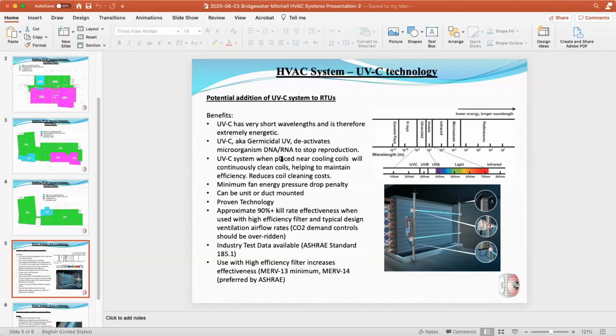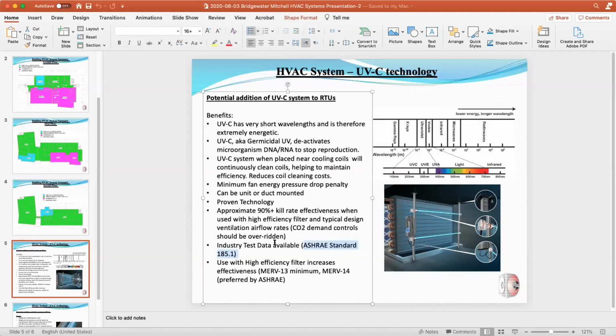That is what's used. It's generated by a bulb that has mercury vapor, and it's generating UV light. They're typically installed in the air handling units on the supply side, at the cooling coil, or within the supply ductwork if it cannot fit in the air handling unit. Approximately, and again, these are some studies, nothing third-party lab certified, a 90% plus kill rate effectiveness when used with high filter efficiencies. During that, you also have to remove your CO2 demand controls or override them. With UVC, there are some standards that must be adhered to, so it's a little bit better than some of the other technologies that might be there.